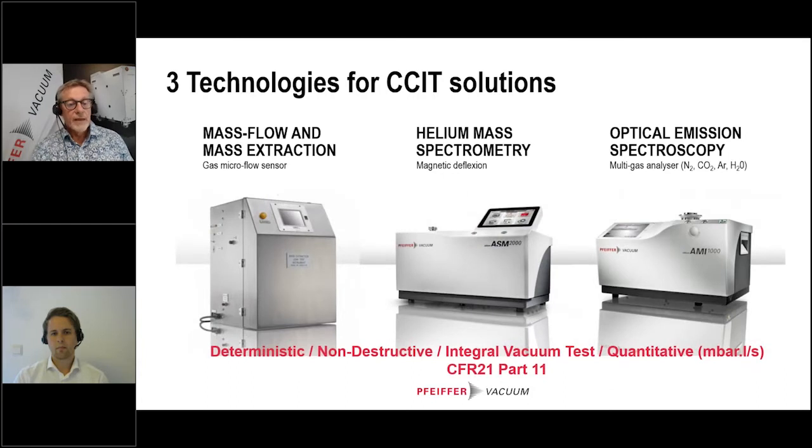So mass extraction and optical emission spectroscopy are easy to understand, do not require any sample preparation, and do not require any tracer gas. But of course, in the end, as you will see in this study, they are less sensitive compared to helium.